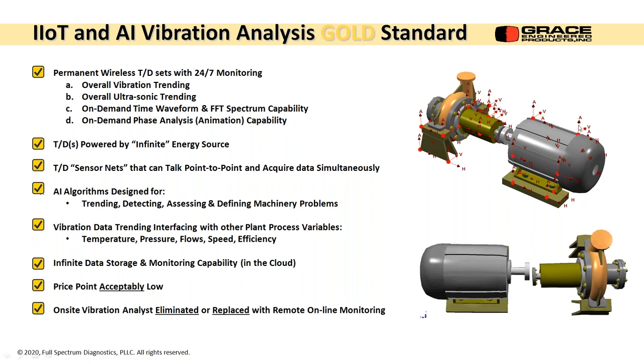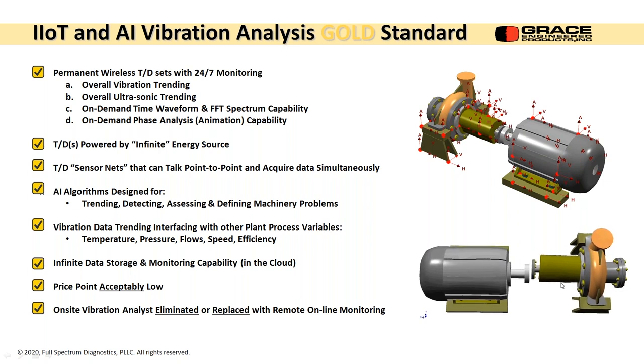I'm showing you a pump, and it probably had 30 measurements on it. And these were all amplitude and phase type measurements. They were all simultaneously acquired. So I can see how the machine's moving, and I can get an animation like this. If we have on-demand phase analysis, meaning can one transducer link and talk to the other one simultaneously, then we can do something like this on a rudimentary scale for every machine. Assuming, you know, things in the future keep going the way they are, and these wireless transducers get smaller and more battery efficient, and you can link them all together on a machine, you can put just a sensor net of transducers on your machine and get all kinds of animation response and phase response.